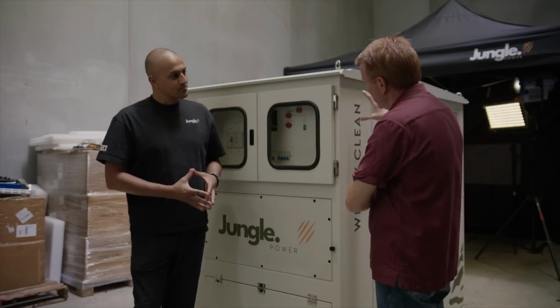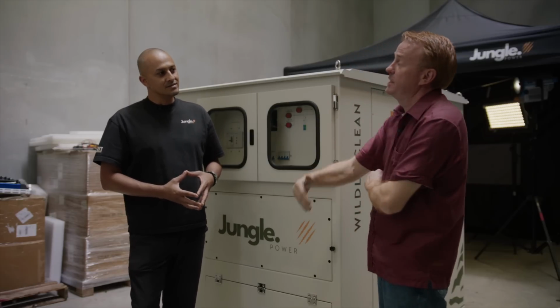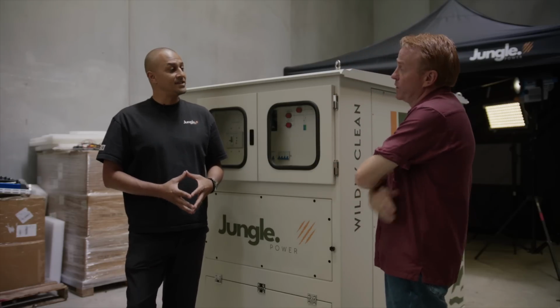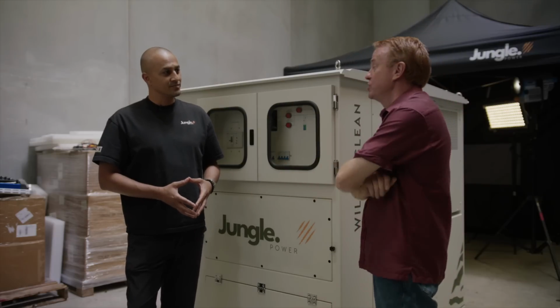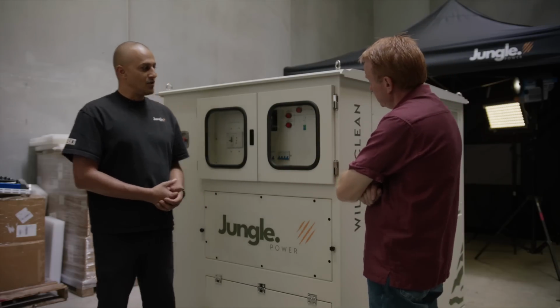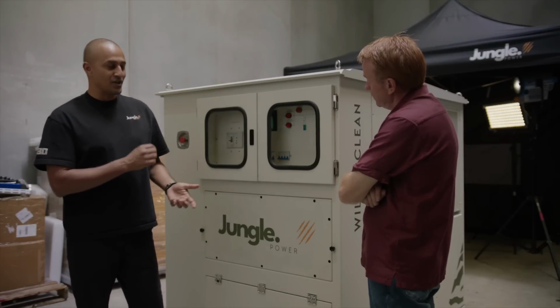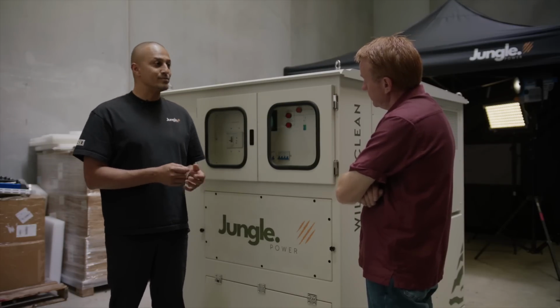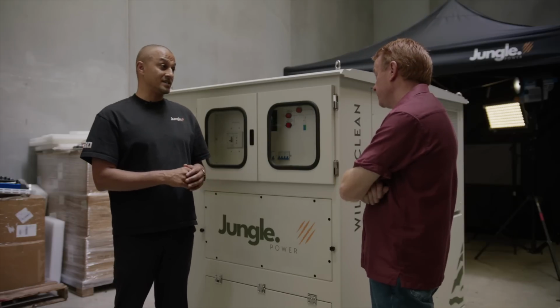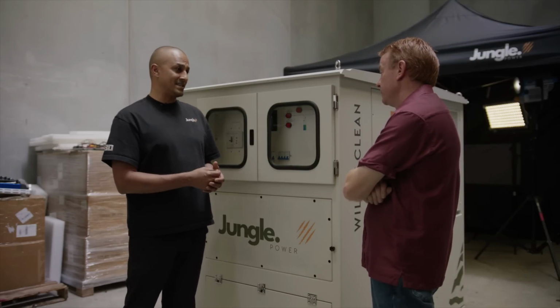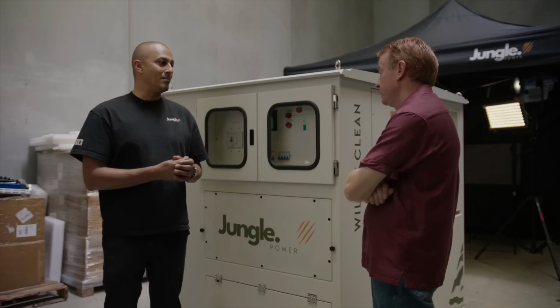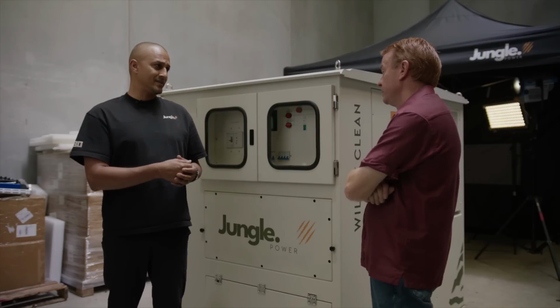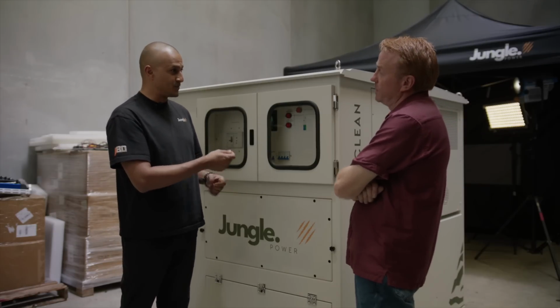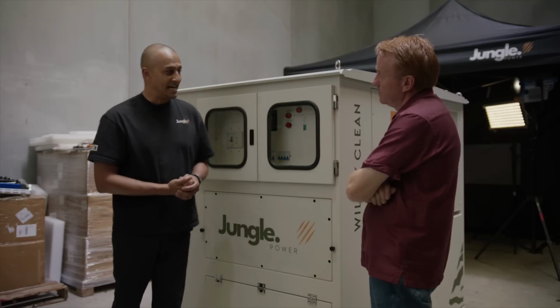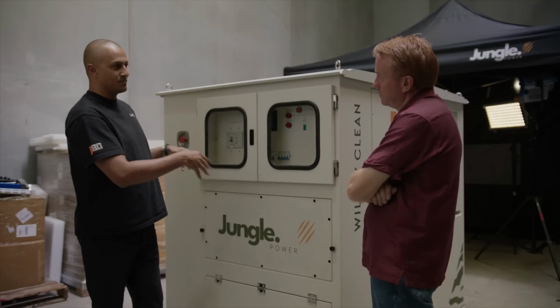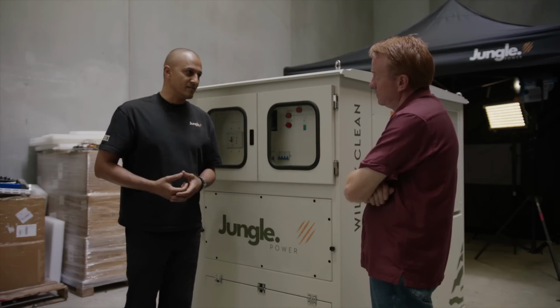So you manage the temperature inside the unit to extend the life of the batteries, and that more than compensates for running the air conditioner. That's the only thing that produces a little bit of sound on the system; otherwise it's dead silent. Even when the AC is on it's just a very low hum. It's a DC powered air conditioning system, 48 volts, running straight off the batteries, which helps optimize the overall efficiency of the unit.